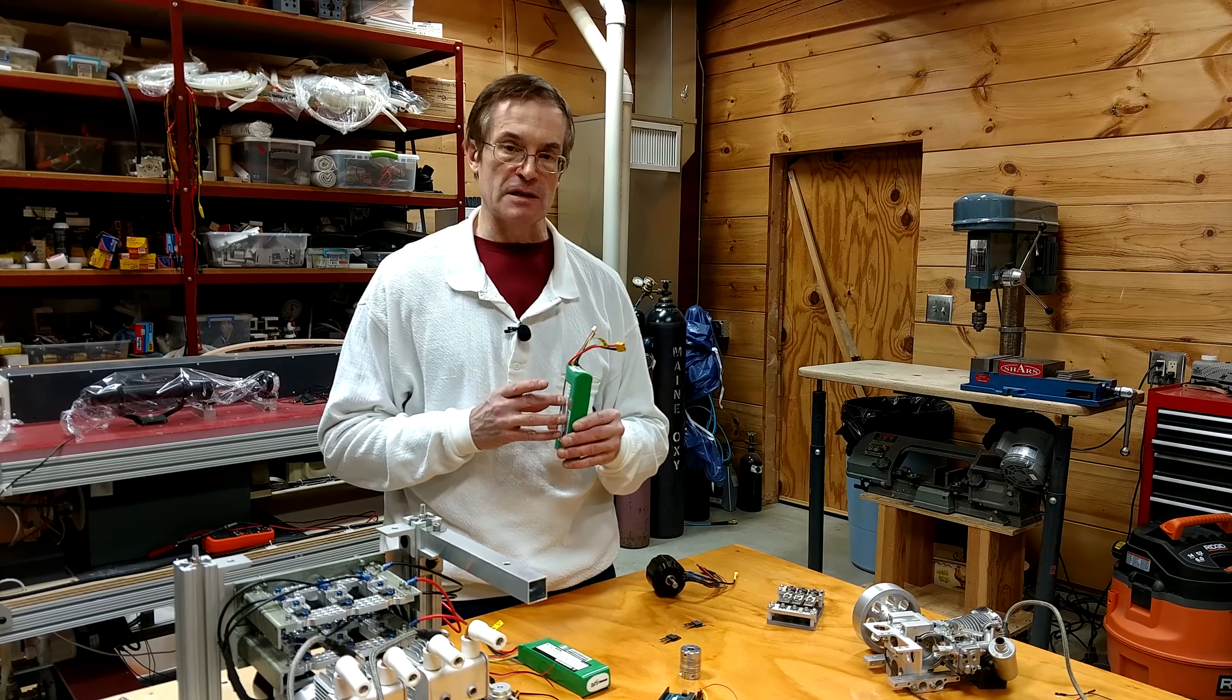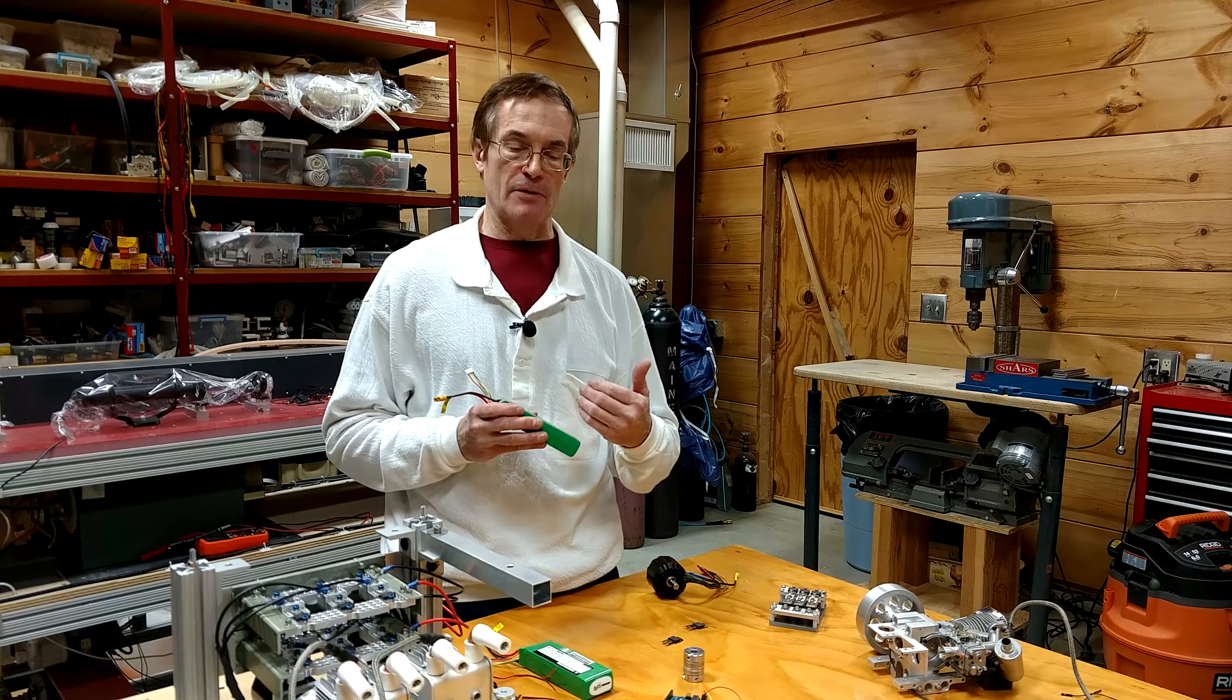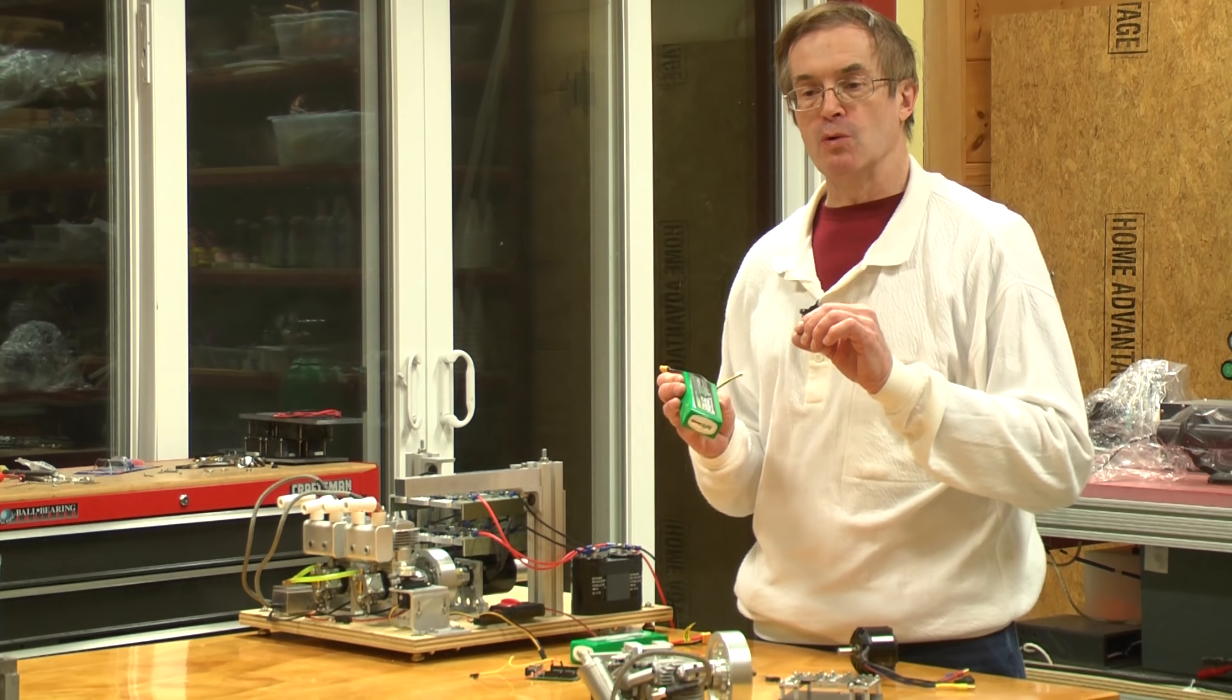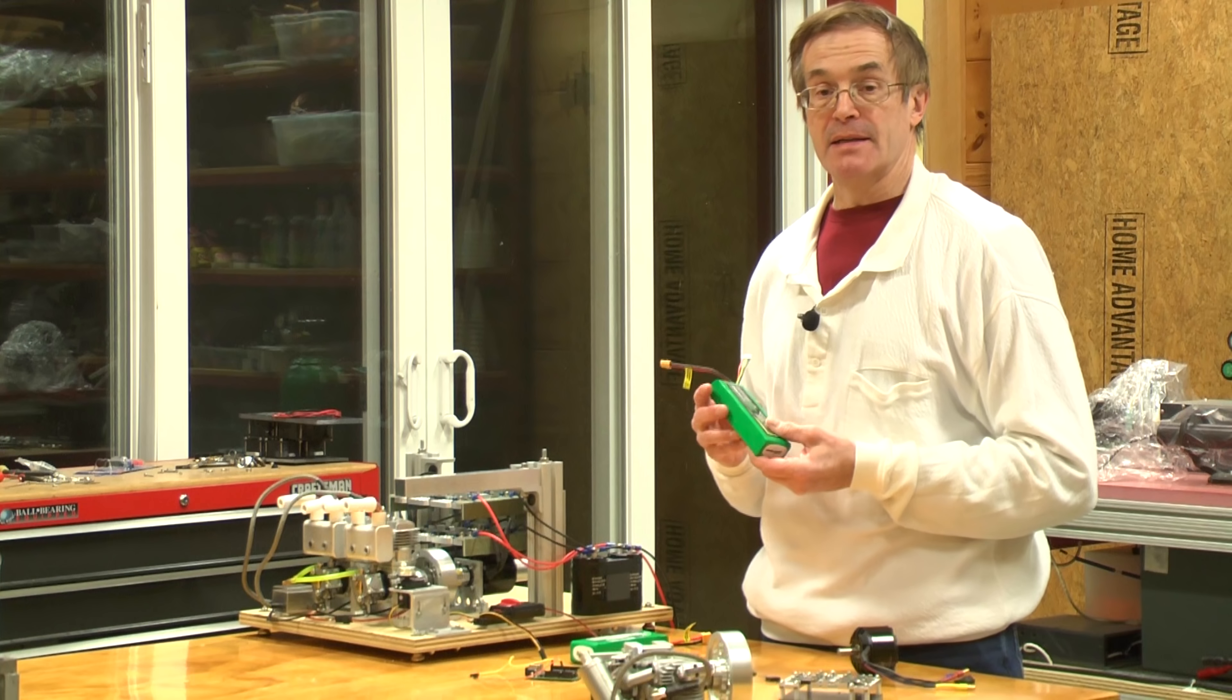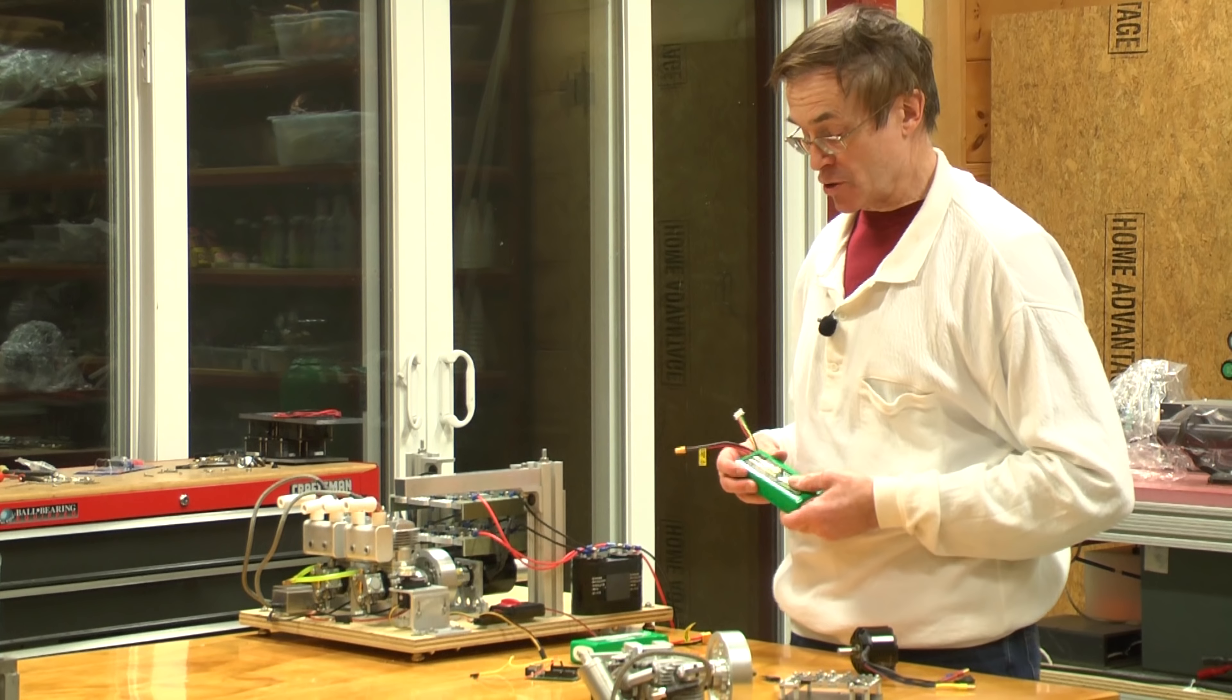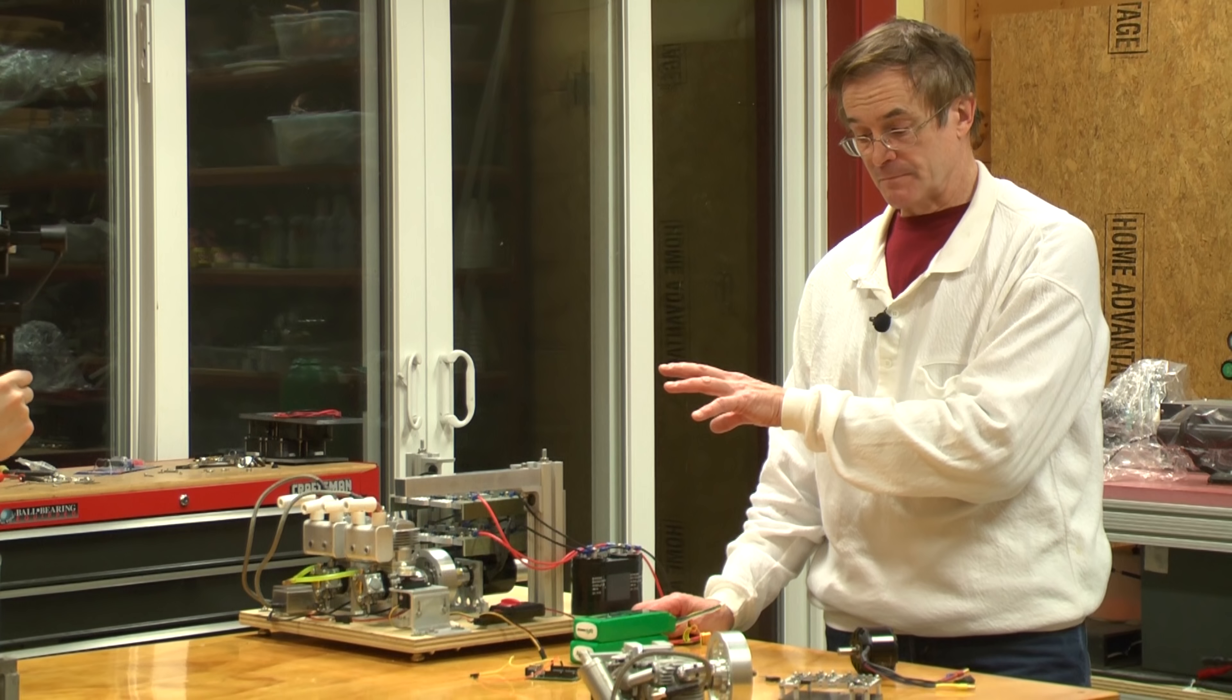It works in reverse too. If I decrease the load suddenly, rather than the generator producing a higher voltage than the bus would desire, the extra current that comes out of the generator will go back into the batteries - they'll actually charge. Furthermore, the engines don't generate absolutely continuous torque - there still are peaks and troughs even in the compression and power strokes. So there's a small varying ripple of about half a volt at about 100 hertz coming out of the engine. The beauty is that the battery system actually helps to buffer that as well.